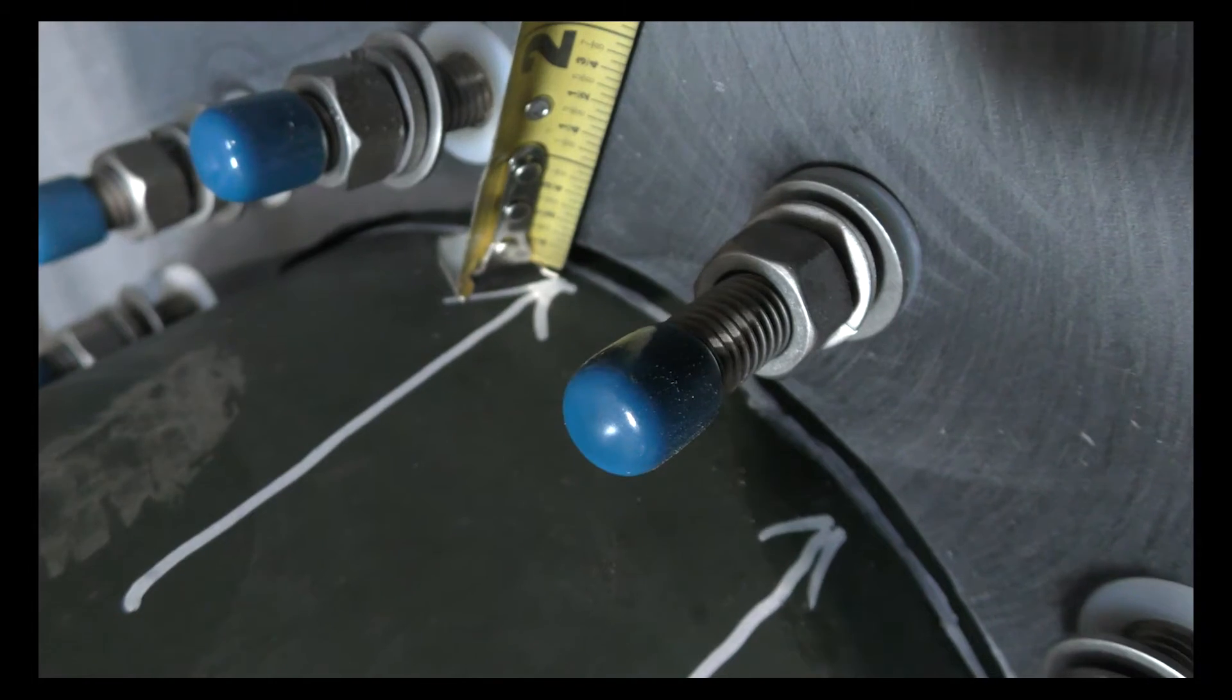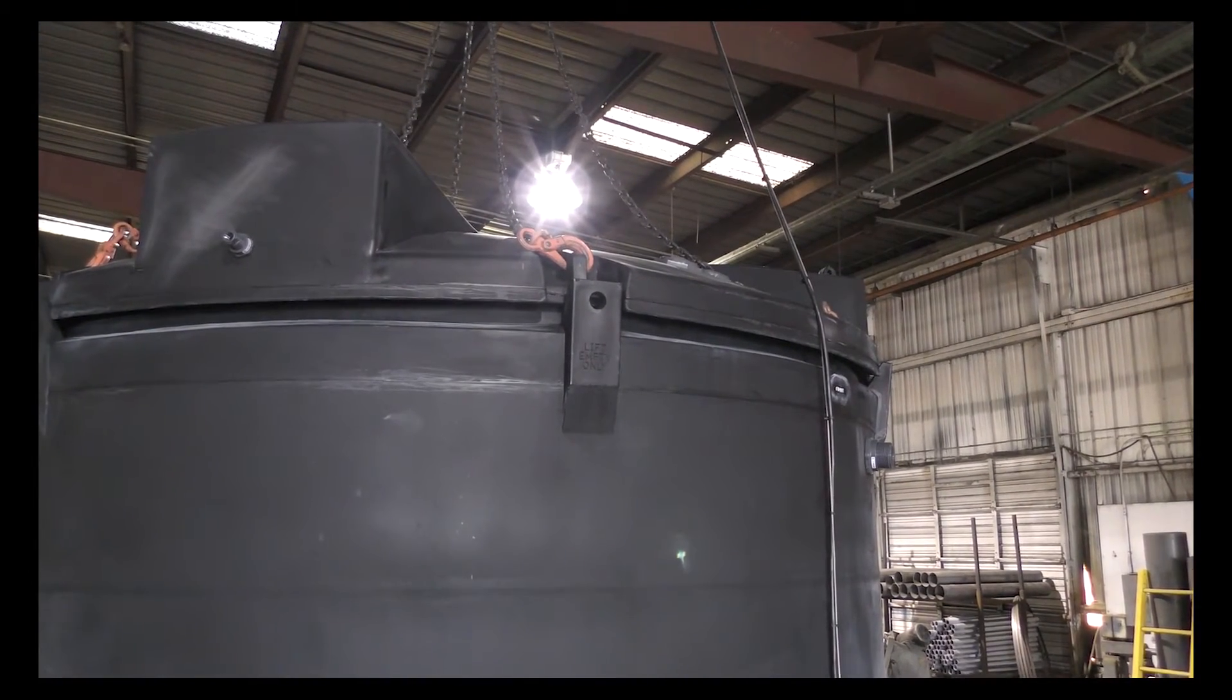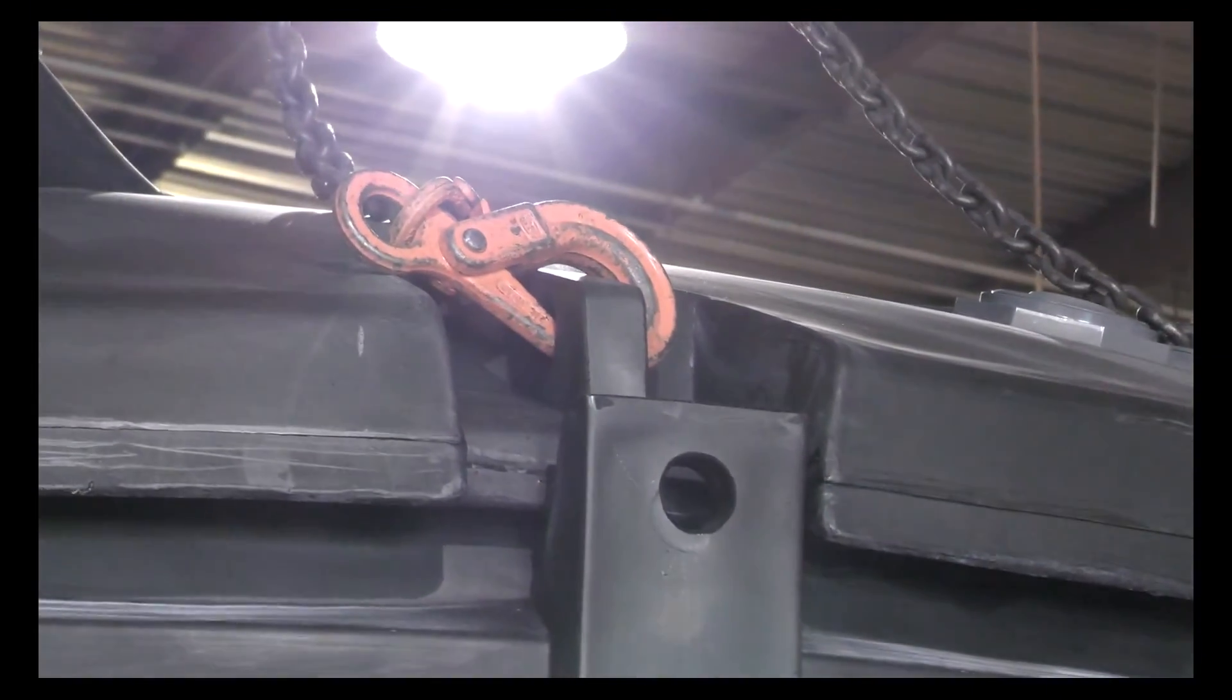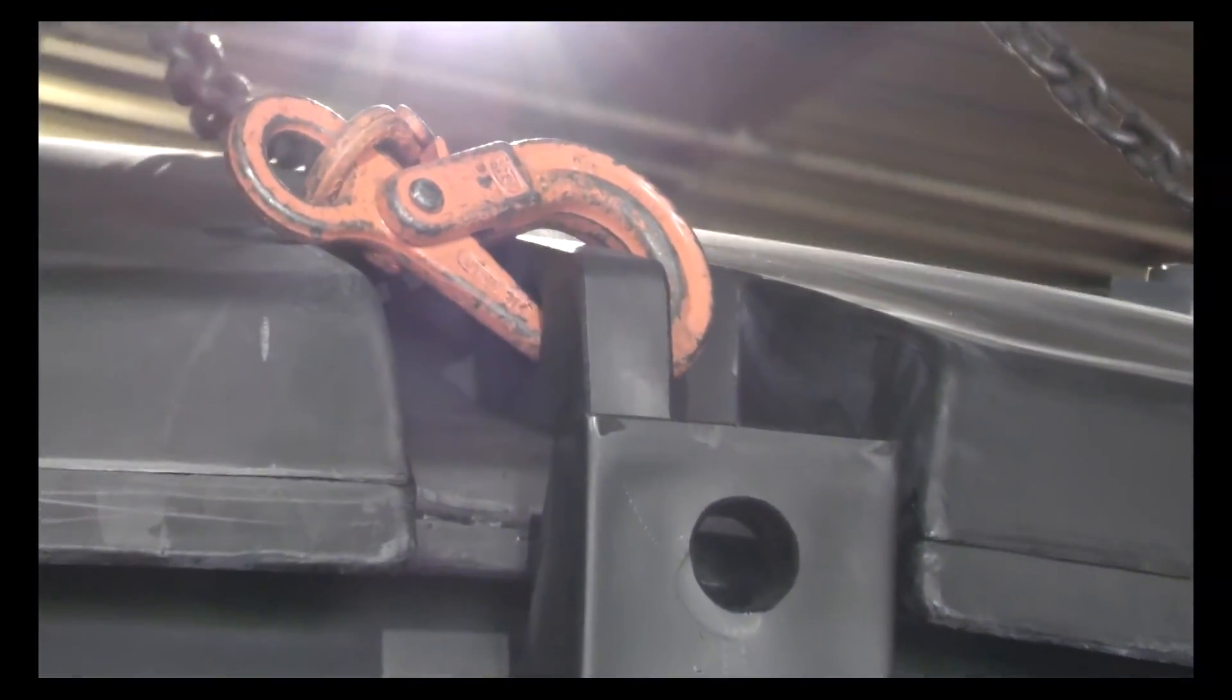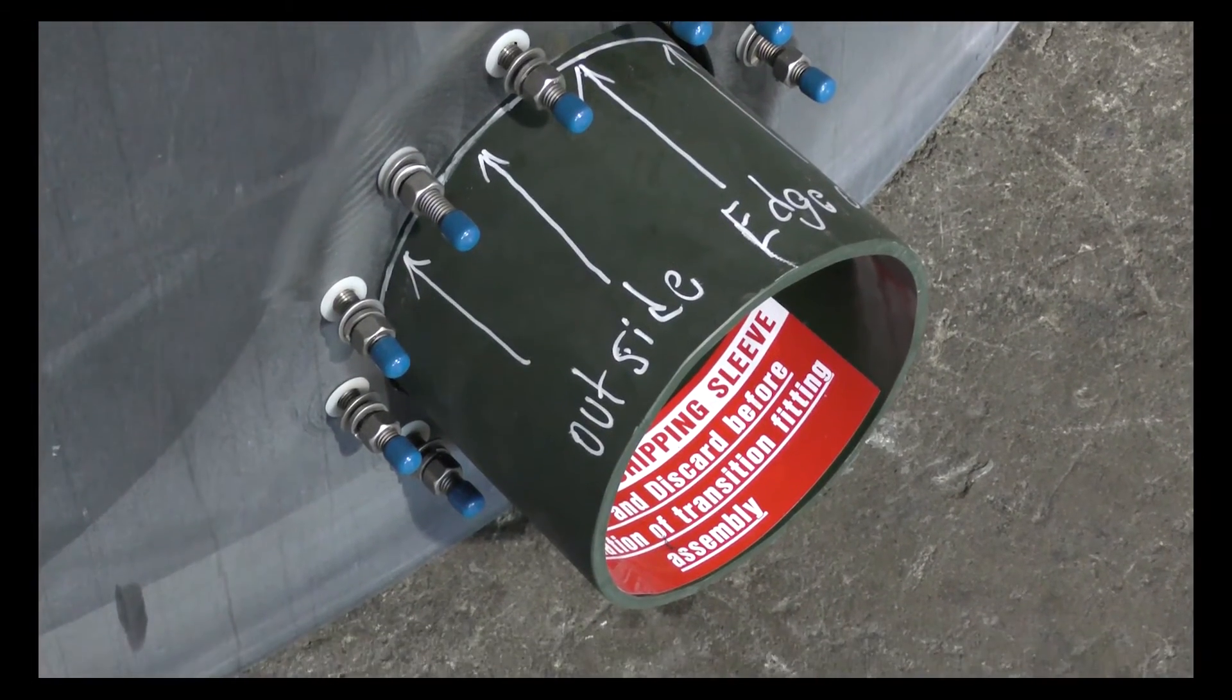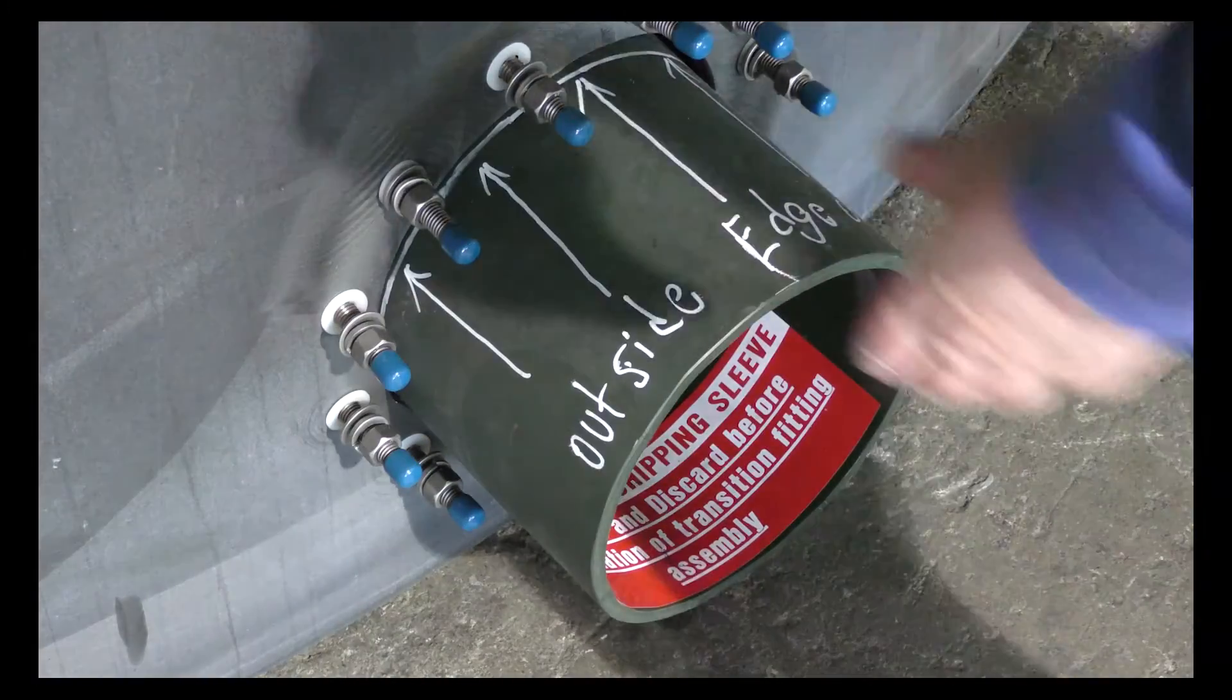If adjustments are needed to the bellows transition fitting, connect your crane or boom truck to the lifting lugs on the primary tank. Lift up on the primary tank slightly, just enough to free up the alignment sleeve for adjustment.